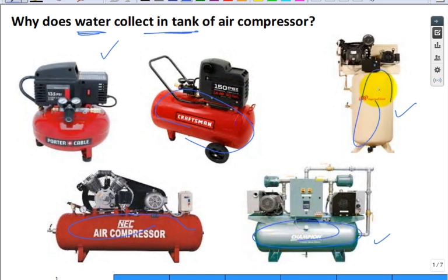And you get water in there and say, where does the water come from? It comes from the air. It ingests air into it, compresses, boosts the pressure of that air, puts it into a tank. The air then cools off back to room temperature if you give it a long enough time. And then when it cools off, it dews out moisture in the tank, and you have to then drain the tank. The big air compressor in the shop, it's like this in the West Campus, has a drain that's automated, and it'll blow down every couple minutes. The first time if you're ever out there, all of a sudden, psh, oh, what's that noise happening? Well, it's automated to purge some little air at the bottom, and if there's any liquid in it, it blows it out. So you don't have to remember to go do that.